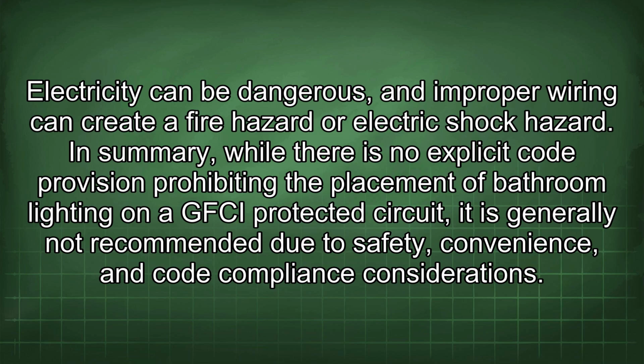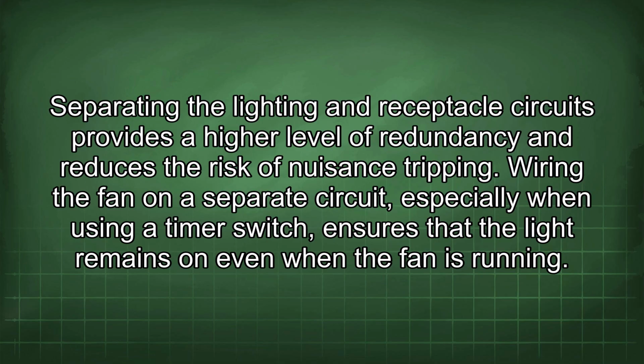In summary, while there is no explicit code provision prohibiting the placement of bathroom lighting on a GFCI protected circuit, it is generally not recommended due to safety, convenience, and code compliance considerations. Separating the lighting and receptacle circuits provides a higher level of redundancy and reduces the risk of nuisance tripping. Wiring the fan on a separate circuit, especially when using a timer switch, ensures that the light remains on even when the fan is running.